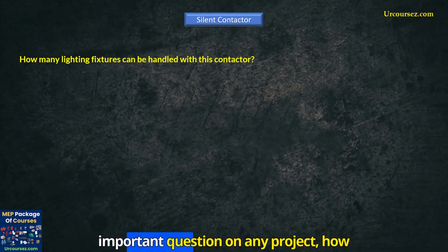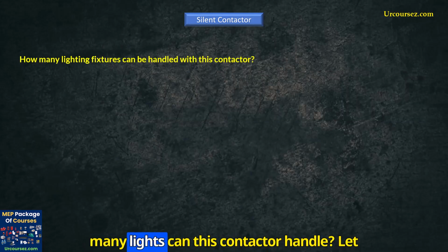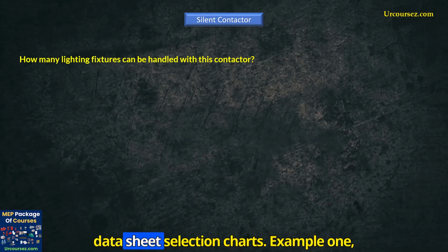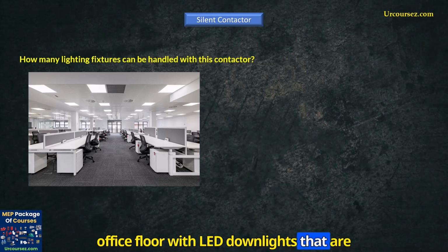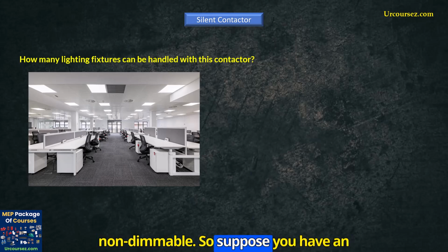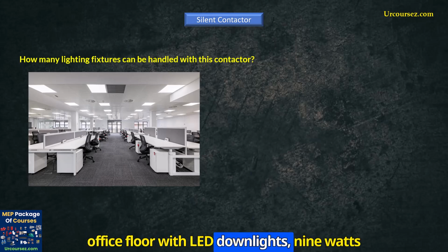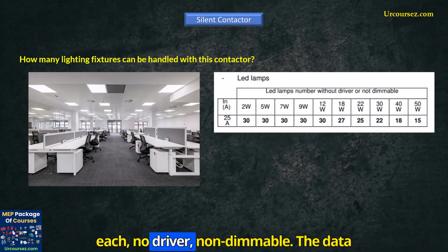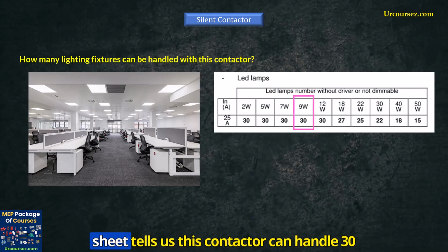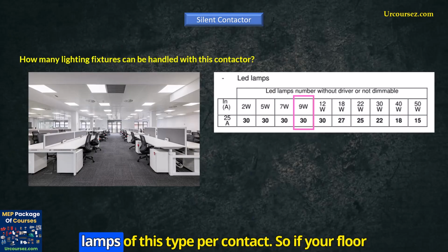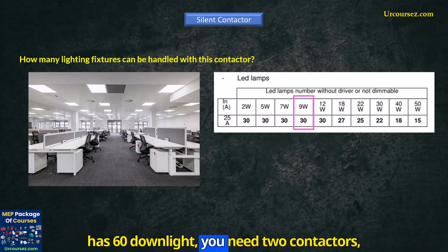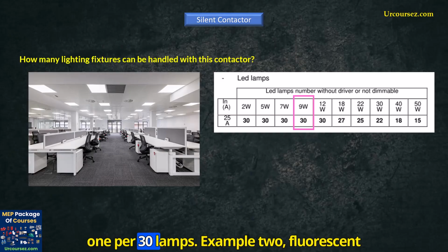Now the most important question on any project: how many lights can this contactor handle? Let me give you practical examples based on the datasheet selection charts. Example 1, office floor with LED downlights that are non-dimmable. So suppose you have an office floor with LED downlights, 9 watts each, no driver, non-dimmable. The datasheet tells us this contactor can handle 30 lamps of this type per contact. So if your floor has 60 downlights, you need 2 contactors, 1 per 30 lamps.